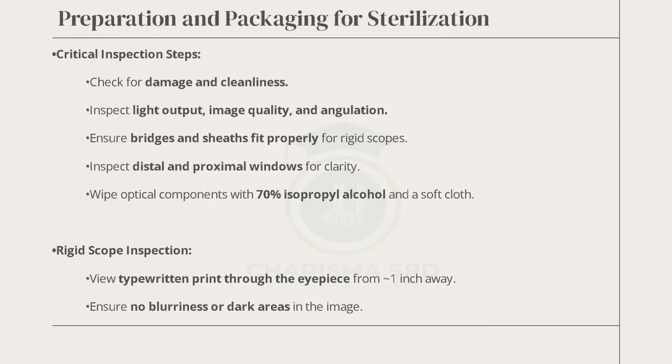Okay. So critical inspection point. The distal tip. Check for cleanness. Check the distal tip. Make sure the light, if it is a rigid one, goes through. If it's flexible, make sure that distal tip is not cracked and what have you. Most of the time, I always tell people, wipe it. I start with 70% alcohol.